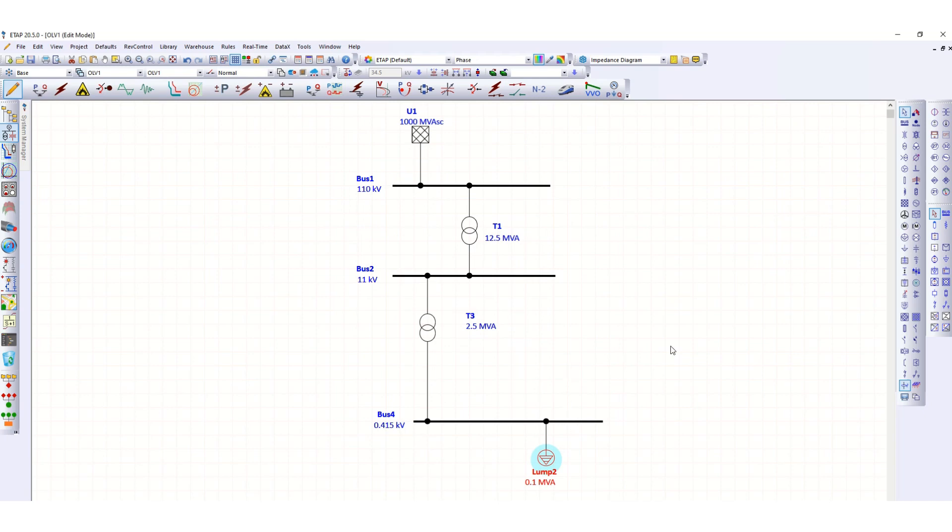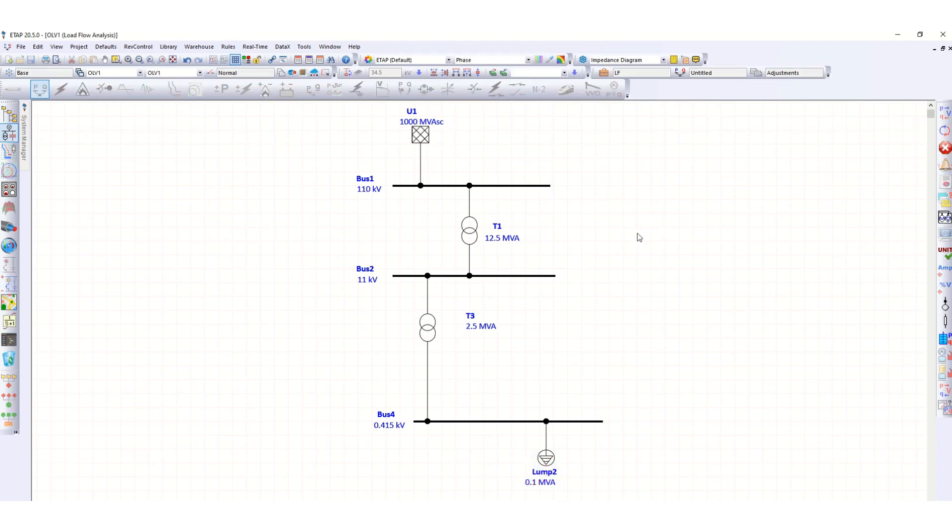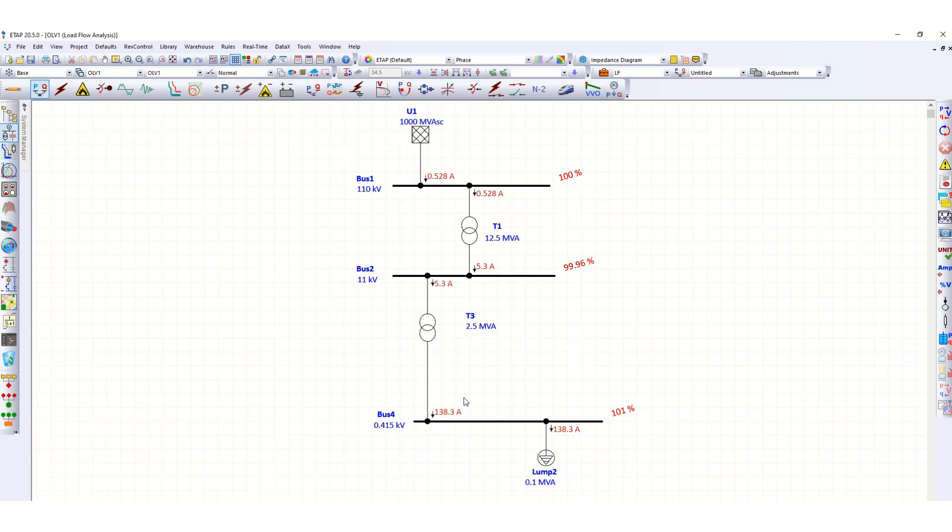Now let's check with the load flow calculation. The 415 volt bus is drawing 138.3 ampere and the bus voltage is also okay.